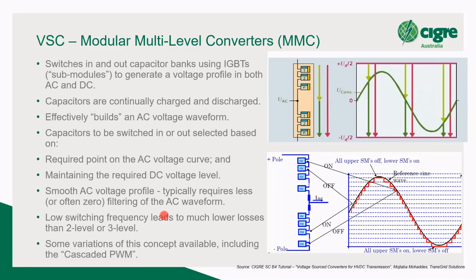So basically, a multi-level uses capacitors that are constantly being charged and discharged by the submodule, switching them in or switching them out or bypassing them completely to build a waveform. And it does it pretty well. If you look at these diagrams here, which I took from a tutorial in Canada, the AC voltage waveform is measured at this point, and you've got your positive and your negative DC voltage. You can imagine these modules here have a polarity, negative, positive, negative, positive, and these have negative, positive, negative, positive. So these are seen as positive to the AC voltage, and these are seen as negative to the AC voltage at that point.